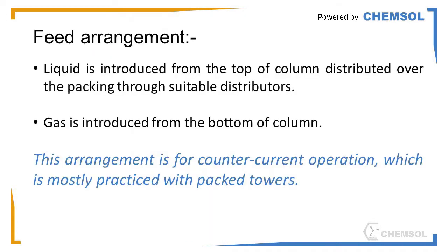Now it's time for feed arrangement. Liquid is introduced from the top of the column and distributed over the packing through suitable distributors. Gas is introduced from the bottom of the column. This arrangement is for counter-current operation, which is mostly practiced with packed towers.